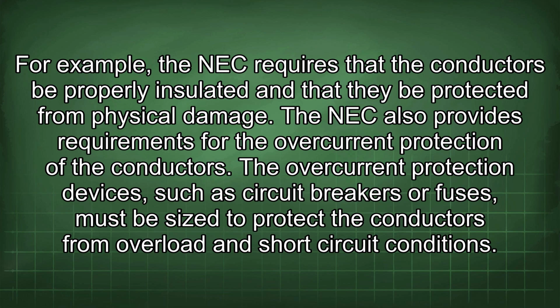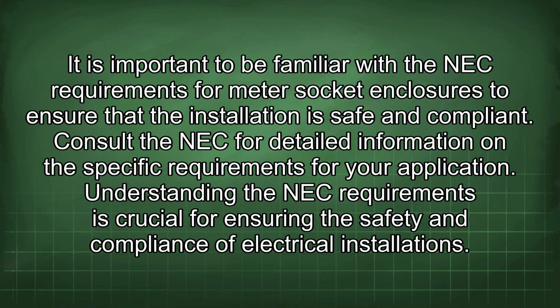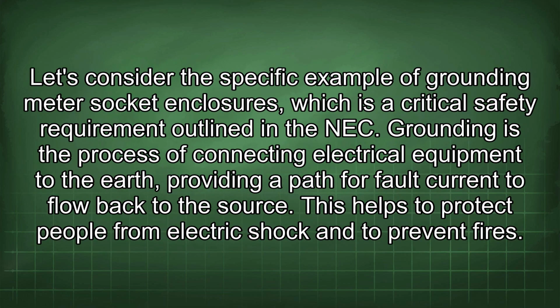The overcurrent protection devices, such as circuit breakers or fuses, must be sized to protect the conductors from overload and short-circuit conditions. It is important to be familiar with the NEC requirements for meter socket enclosures to ensure that the installation is safe and compliant. Consult the NEC for detailed information on the specific requirements for your application. Understanding the NEC requirements is crucial for ensuring the safety and compliance of electrical installations. Let's consider the specific example of grounding meter socket enclosures, which is a critical safety requirement outlined in the NEC. Grounding is the process of connecting electrical equipment to the earth, providing a path for fault current to flow back to the source. This helps to protect people from electric shock and to prevent fires.